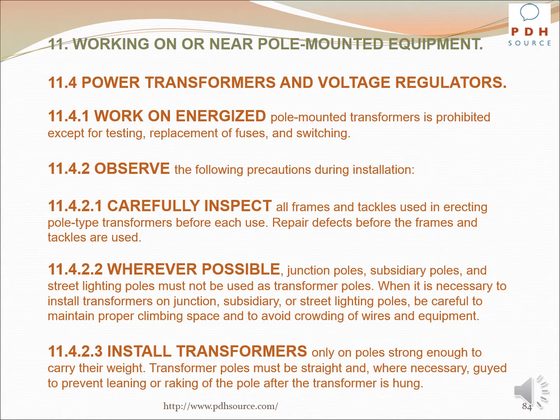Wherever possible, junction poles, subsidiary poles, and street lighting poles must not be used as transformer poles. When it is necessary to install transformers on junction, subsidiary, or street lighting poles, be careful to maintain proper climbing space and to avoid crowding of wires and equipment. Install transformers only on poles strong enough to carry their weight. Transformer poles must be straight and, where necessary, guyed to prevent leaning or raking of the pole after the transformer is hung.